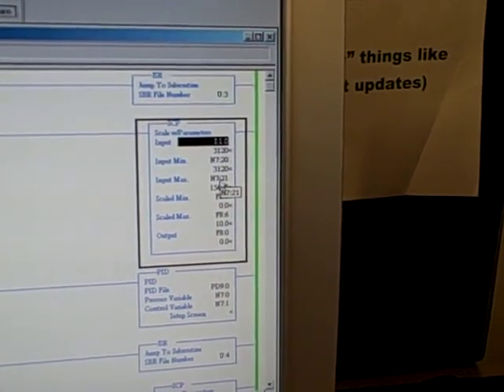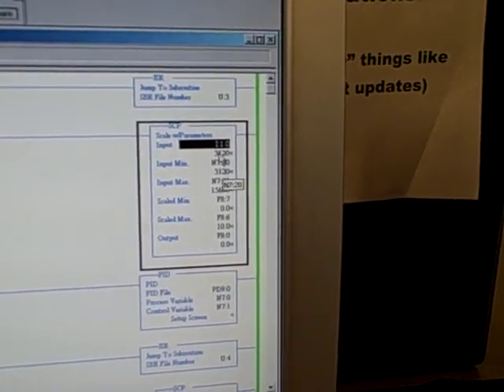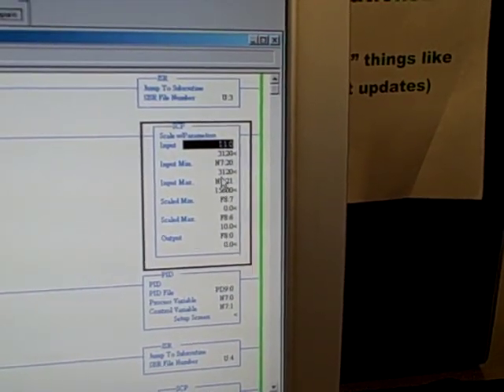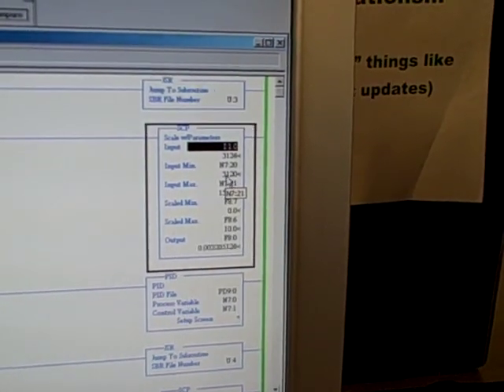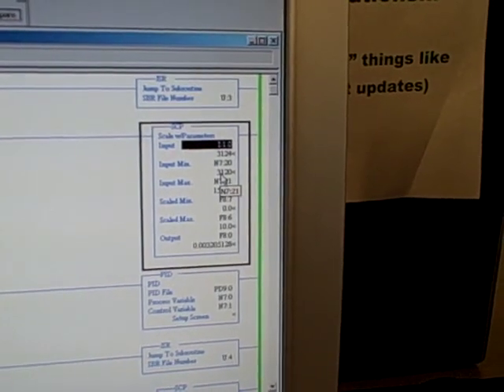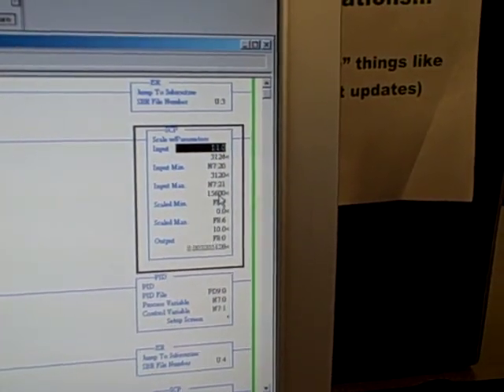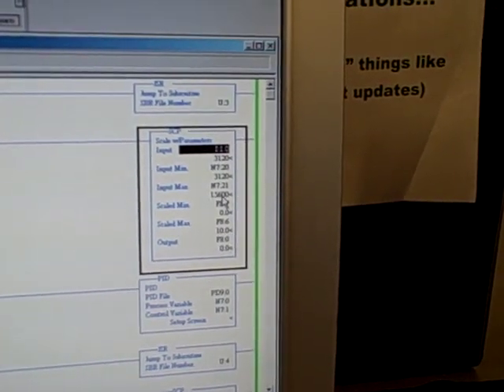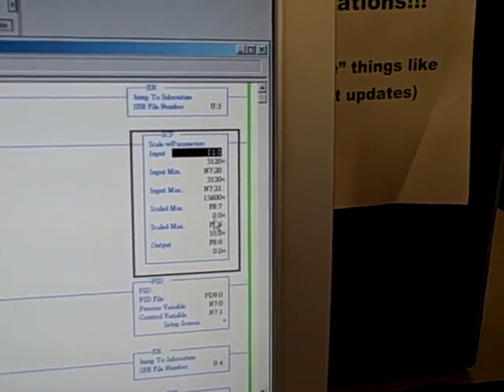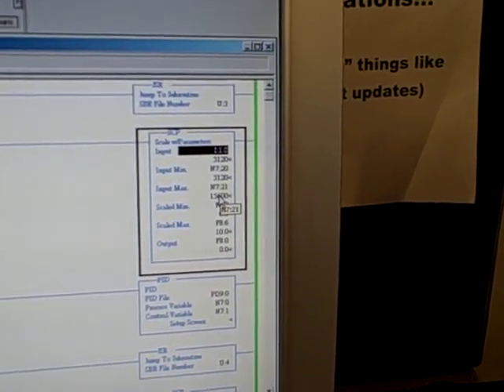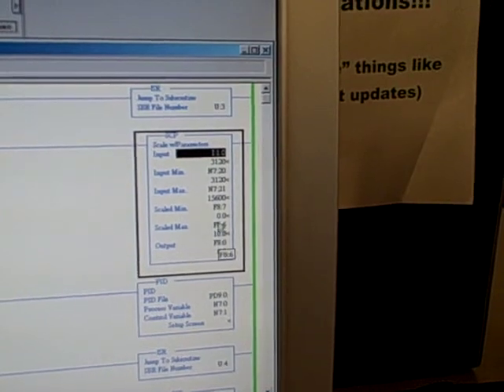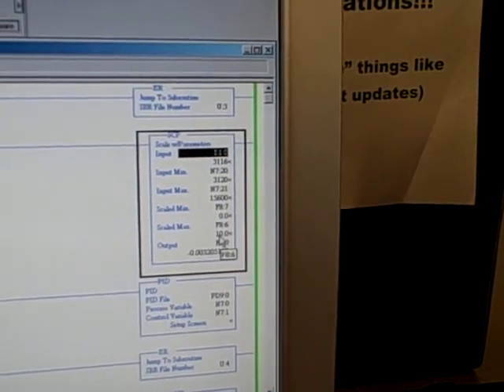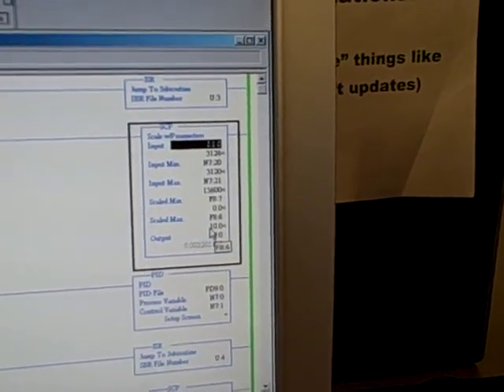The raw count values here, the 3120 or the 15600, that comes from the A to D card, and 3120 is nominally what you should get with 4 milliamps of current, and 15600 is nominally what you should get for 20 milliamps of current. We use the scale instruction here to scale those raw count values into some sort of engineering units so it will make more sense on an operator's display.